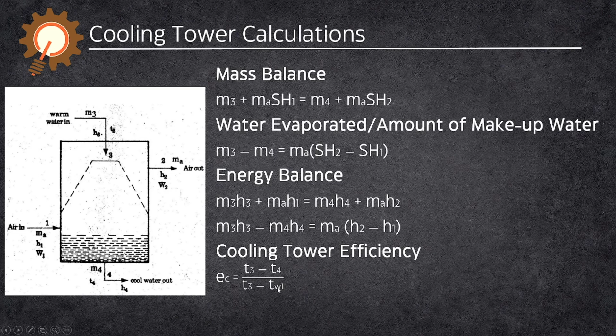Energy balance naman: M3 times H3 plus MA times H1 ay equals to M4 times H4 plus MA times H2. I-transpose lang natin ang M4 at ang MA H1, kaya makukuha natin ay M3H3 minus M4H4 ay equals to MA times quantity H2 minus H1. Ang formula naman sa pagkuha ng cooling tower efficiency ay equals to temperature 3 minus temperature 4, over temperature 3 minus wet bulb temperature at point 1.